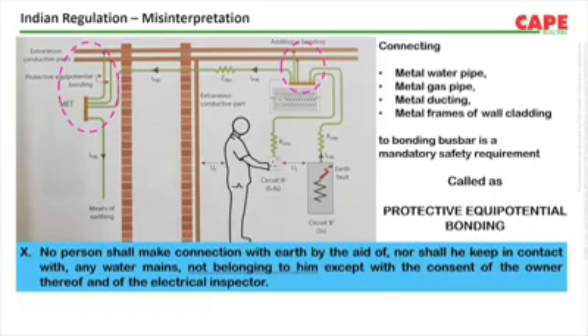What about your own pipe? For example, the metal pipe of a fire sprinkler system. Your pipe must be connected to the MET. This is a mandatory requirement which an electrical engineer is supposed to know and follow. How to connect and where to connect are explained in the relevant standards. There is no need of explaining this mandatory protective measure called protective equipotential bonding everywhere. But the problem is misinterpretation.